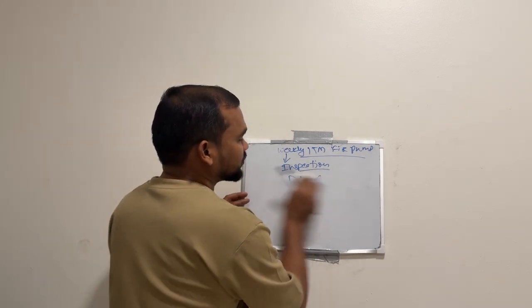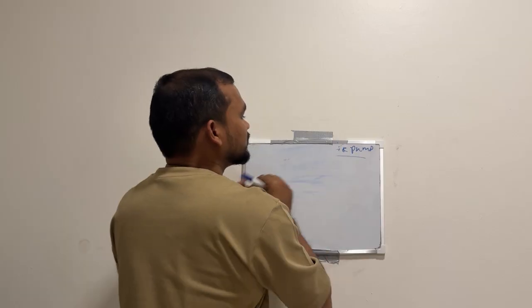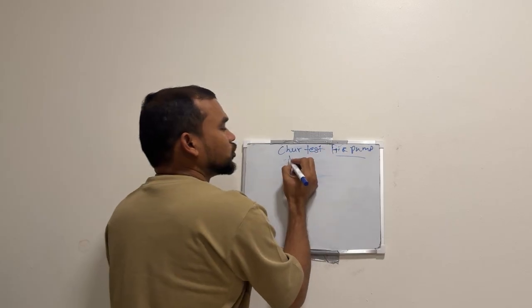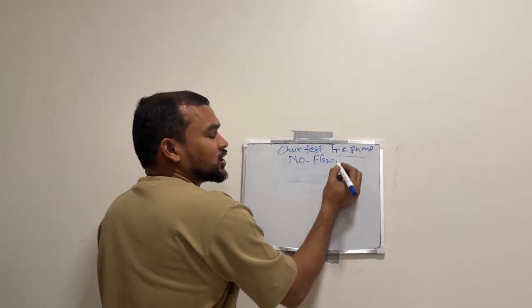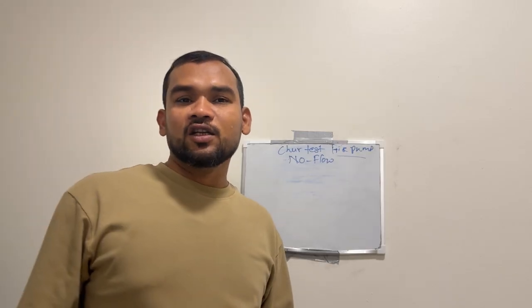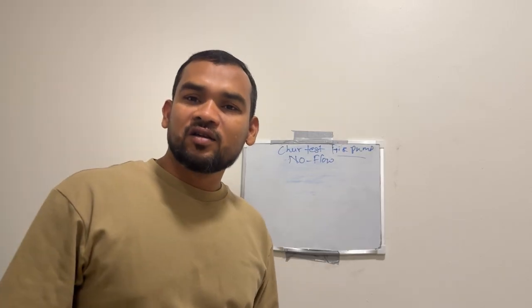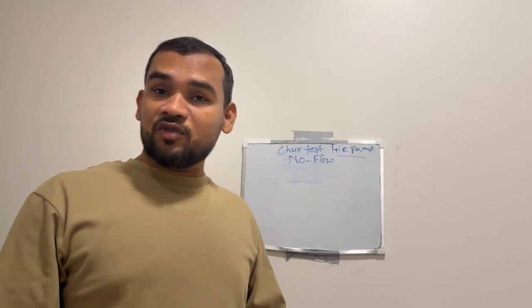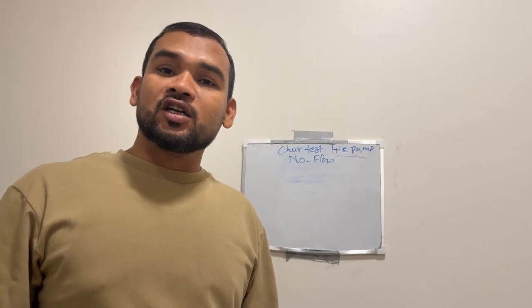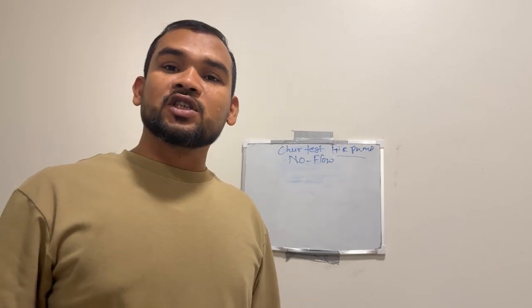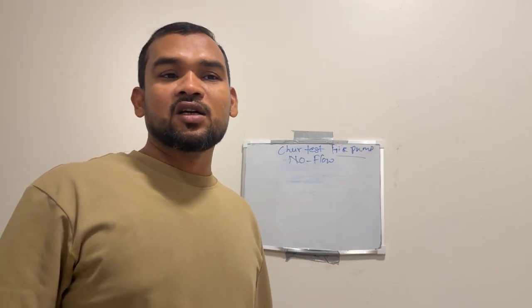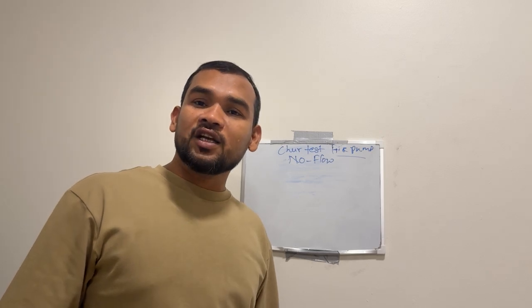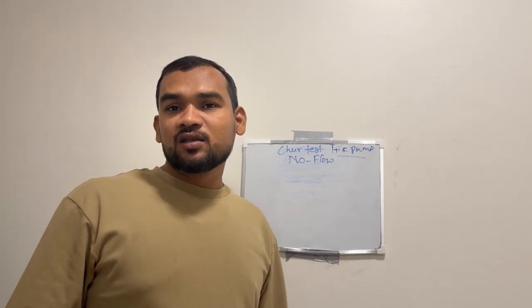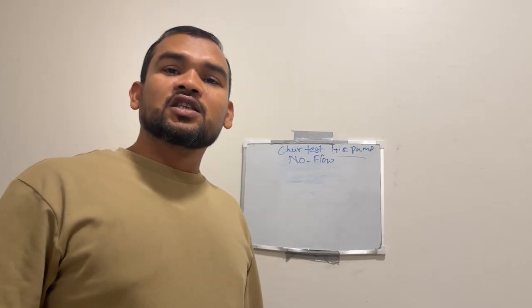Now topic number 2 is the churn test. We also call it a no-flow test, because water is not flowing in the system in the field. So we have to verify. First we do the visual inspection like I described before. Diesel engine, electrical controller, we have to verify the pump house, pump system conditions, suction pressure, discharge pressure, any abnormal conditions, overheating. So we have to verify all of these things before we start the test.